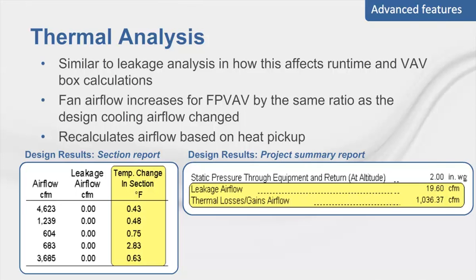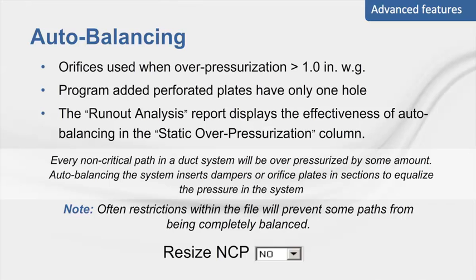The temperature change is displayed on a section-by-section basis in the design results section report, and the total airflow added to the system is displayed on the project summary report. When auto balance is selected, the program will add dampers and adjust them in sections where over-pressurization is present to decrease the excess static available. Perforated or orifice plates are added to sections with over-pressurization exceeding one inch water gauge for acoustical purposes. Dampers or plates added by the system contain the prefix AUT in their fitting ID. To remove program-added fittings, uncheck the auto balance checkbox. Sections can be set to have no fittings added despite being over-pressurized by selecting the don't add dampers/orifices checkbox on the sections tab.